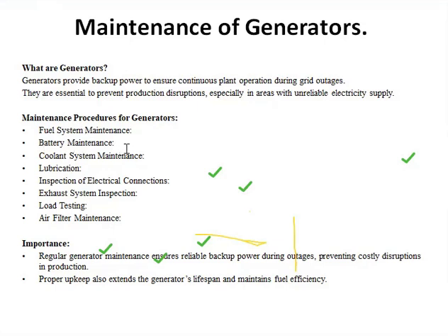So we always check the batteries. Always make sure that the battery voltage is working very well. It is at the required level. Our generator uses a battery of 24 volts, so we always make sure it is at 24. Regular testing of the generator batteries is to ensure that it holds a charge that is enough to make the generator run. A generator that won't start during an outage due to a dead battery could make the operation not successful, like we don't run. And each day there is a set target that you're supposed to produce. So any failure of these systems can lead to us not getting the required targets set by the administrators.